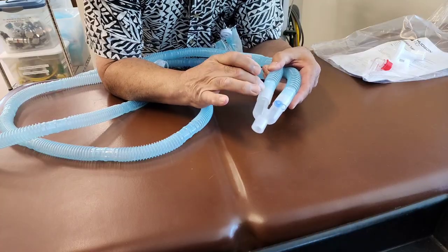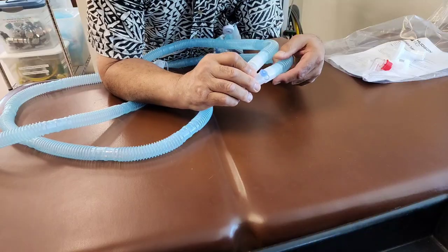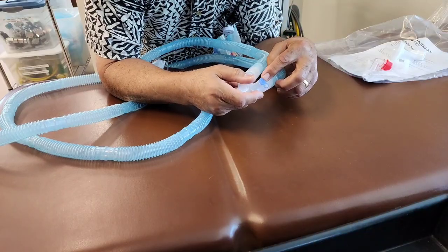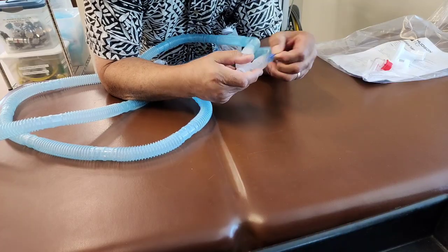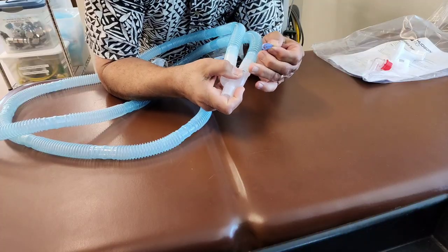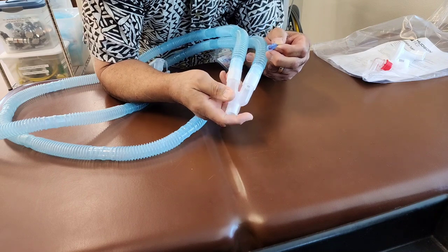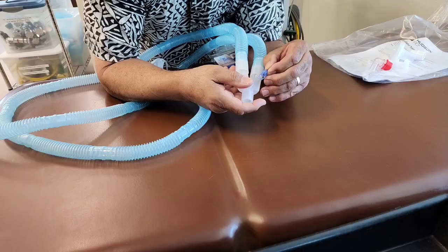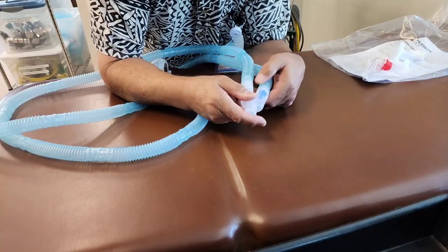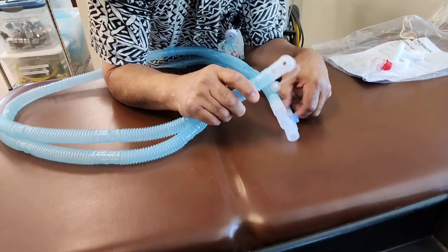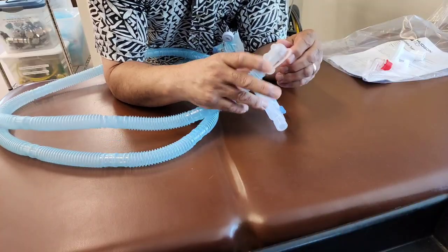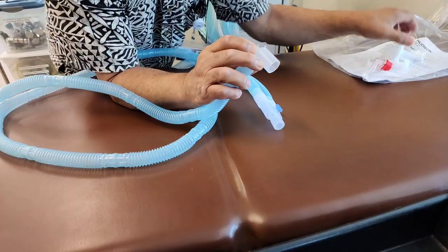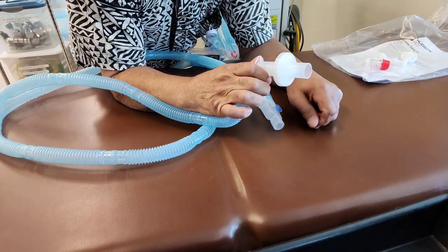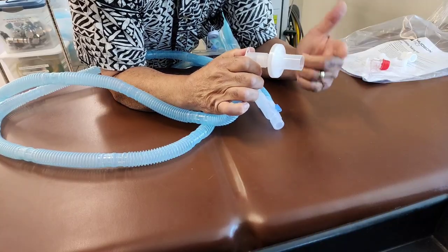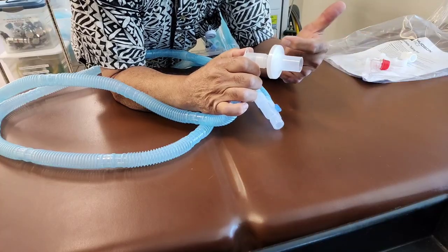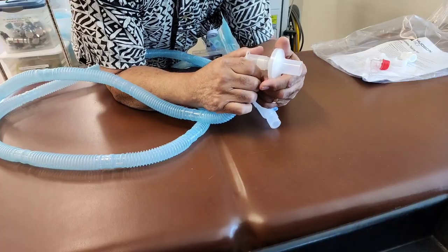So the Y has a couple parts to it here that were actually one part, but the inhalation and the exhalation tubing connect. Okay, this is the inhalation side because there is a little port right here. If you open this up, you'll attach a temperature probe right here, and it goes all the way to the other end of the circuit, and I'll show you that here. Cap that off. The other end of the circuit's right here. This is the inhalation that's coming. We're going to connect this part here to the bacteria filter, and the other part we're going to connect to the ventilator where it's going to the patient, and the ventilator does have a place where it tells you where to connect.